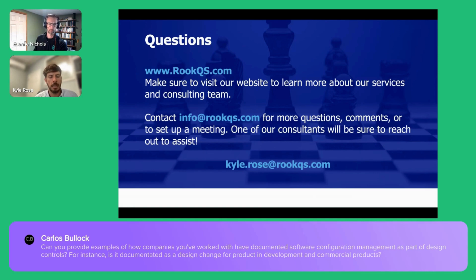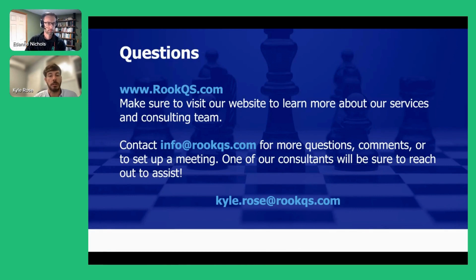Yeah, so this would be part of ongoing design change activities once the product is released, I think is what she's asking. So you would have the configuration management plan in place on what you're going to do and how you're going to manage releases, and then have this software change control process documented once your product is in the commercial phase. The version control during the design phase should also be captured, right? The FDA wants to see your unresolved anomalies and your version history and what was changed and how that related to any fixes. So all that should be documented in both the design phase and post-market phase, as part of your plan and then your formal change control process.